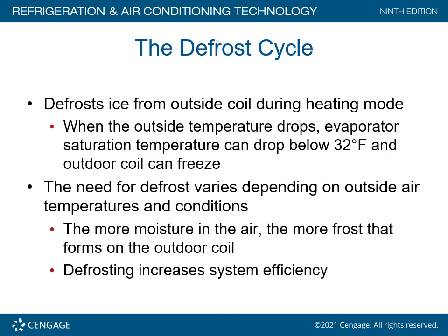The more moisture in the air, the more frost that forms on the outdoor coil. If you have dry, cold air, like in North Dakota, or I should say Phoenix, Arizona, no problem. If you're up in the Pacific Northwest, like Port Orchard, Washington, as an example, you're going to probably have more moisture in the air. That means ice is going to build up a lot faster. Defrosting increases the system efficiency. We want to keep the frost off the outdoor coil in order for that heat pump to work correctly.